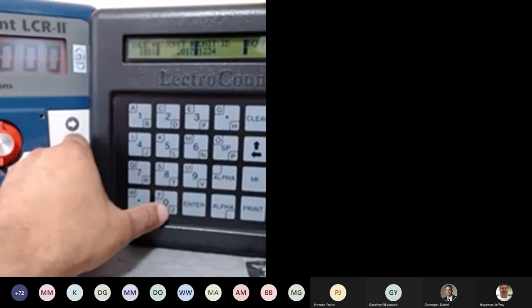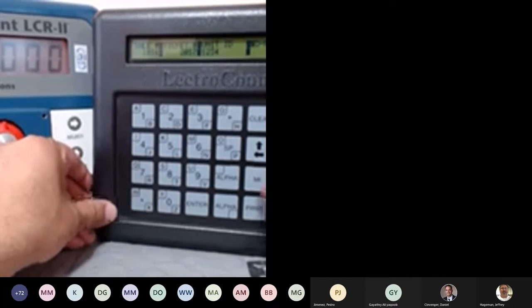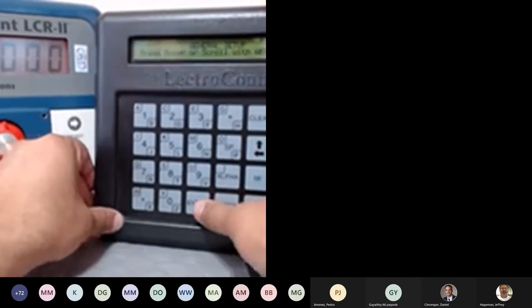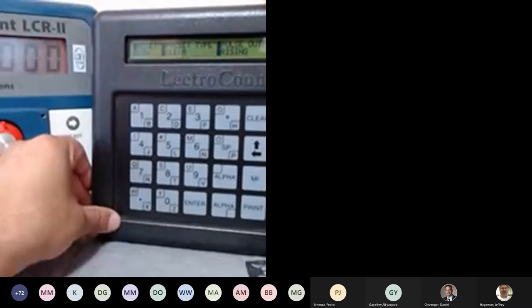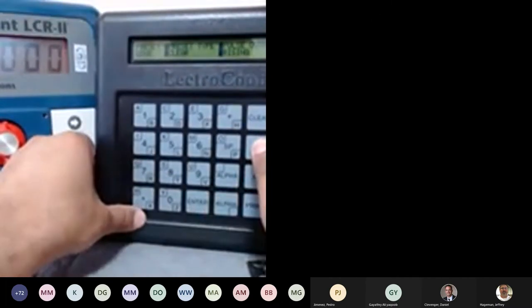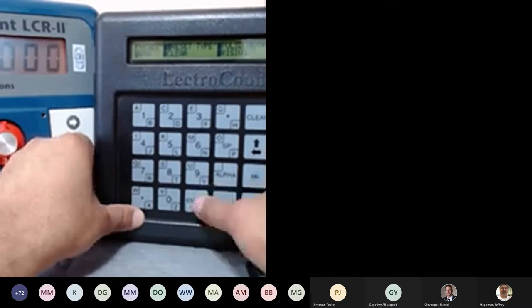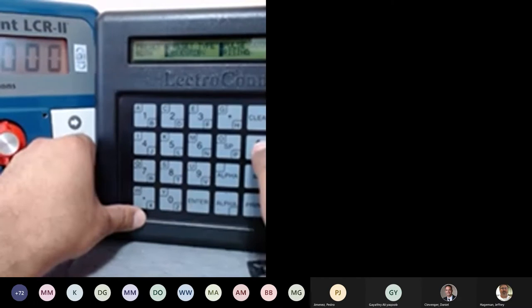This is just a no flow timer. I can just change this to zero if I want to. Now, depends what ticket format I have, I'm probably going to have a multiple delivery at one site message because I set the no flow timer to zero. So basically I can scroll through more preset types. I can change that to whichever I want, net, both, or gross. And same thing with the preset clear or required or inventory or retain, I can do that.